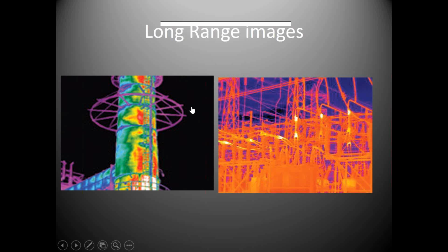The other picture is a substation at an Alcoa. It was an electric melting plant for melting aluminum, but look at all the hot spots in the substation. Are those issues? Is it normal? I don't really know. The picture showed that there's potential issues in this substation that could cause this plant some major cost. Easy to see, easy to find with a camera.